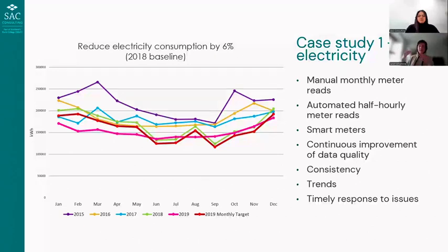Now, the downside is that utility meters tend to be very often in areas that just don't have very good reception. For the shopping center, it was back of house, at the back of the building. They can be somewhere in a cupboard, in the cellar, in the loft. And quite often those are not places that have very good reception, like normal mobile reception, because they just have SIM cards in them, which means there could sometimes be problems with sending and receiving the data.